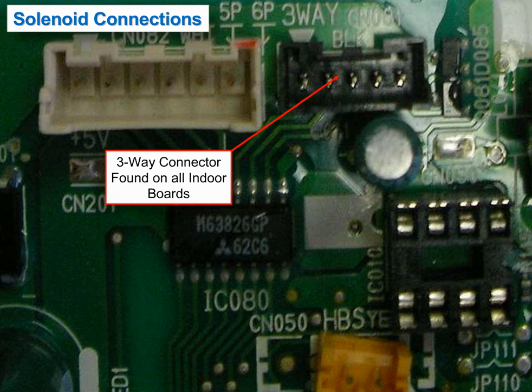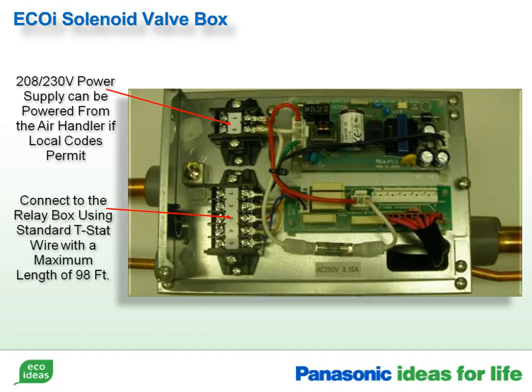This is the 3-way connector located on the main board. It can be found on all of the indoor units. This is the solenoid valve box. Terminals 1 through 5 are for the control wiring that connects to the relay box. Above that are the terminals for the power supply. If local code permits, you may connect the high voltage from the air handler to the solenoid box.